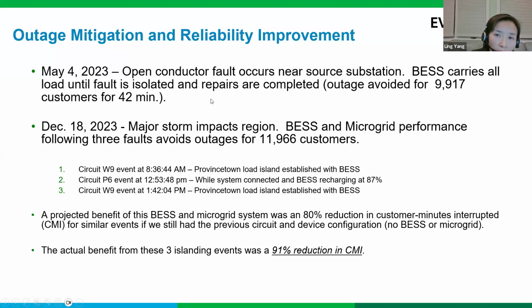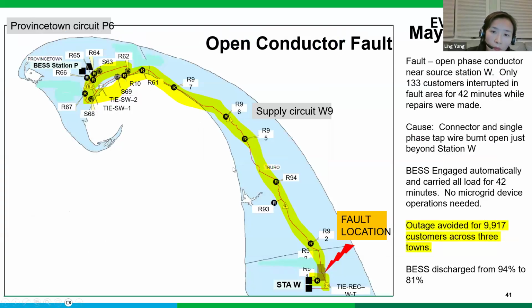In May last year, there was a fault near the supply source station, and the battery carried almost 9,900 customers for 42 minutes. This is the schematic of the supply station, this is the distribution supply, and here is the battery station. As I mentioned, this is a 13-mile, 23 kV distribution circuit, and the majority of the load is right here. About 50% of the circuit loading is right around where the battery is.